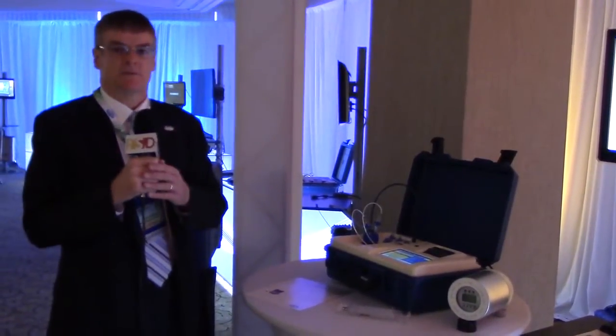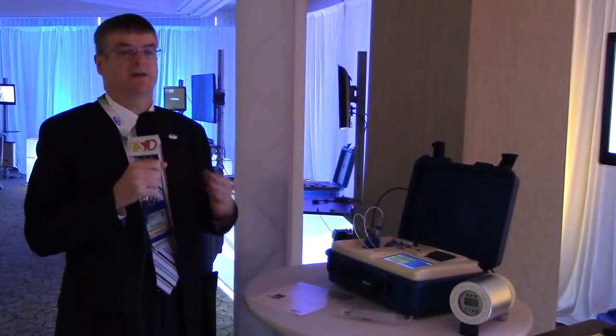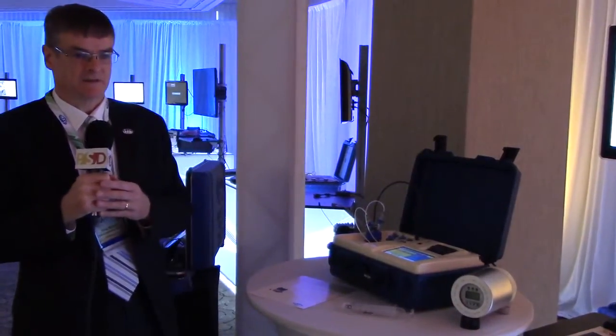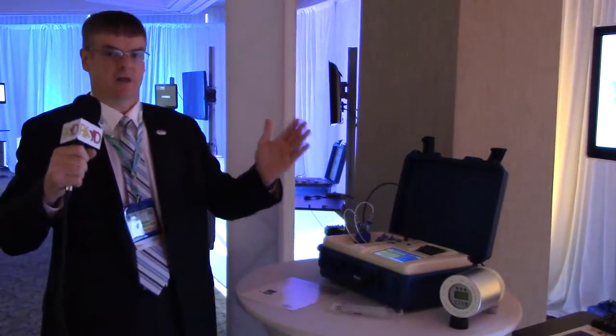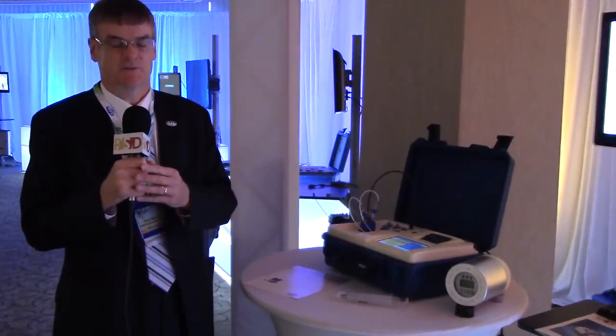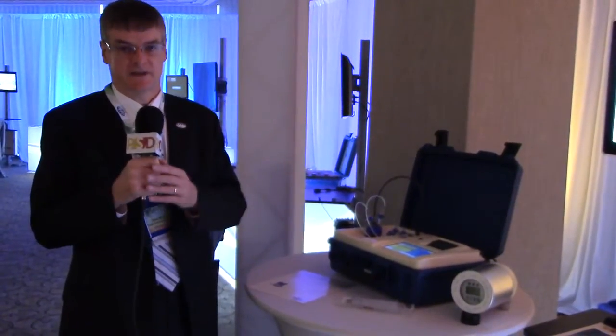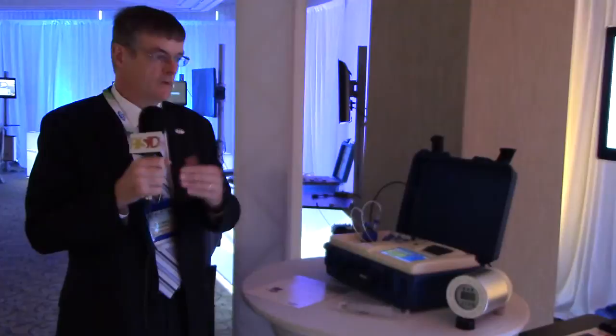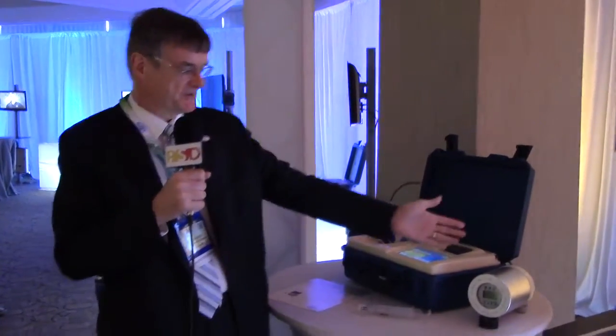In the world of monitoring over the years, power transformers have become more and more critical, more and more reliant on the latest technology. What we found is that monitoring has developed such that over many years large online systems were developed which produced large amounts of results, interesting data, power transformer analysis. And these were expensive, high-capital items to go on the transformer, which is itself a large, high-capital item. Over time, people have realized that there's a more efficient asset management approach. What we recommend is that for most transformers, we would produce and supply a small check transformer type of device.